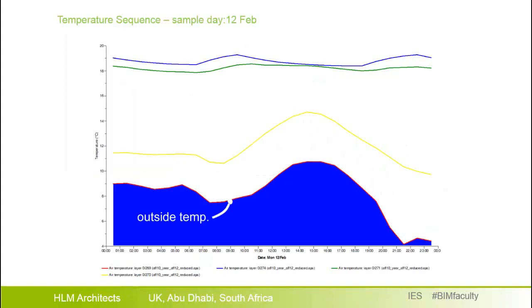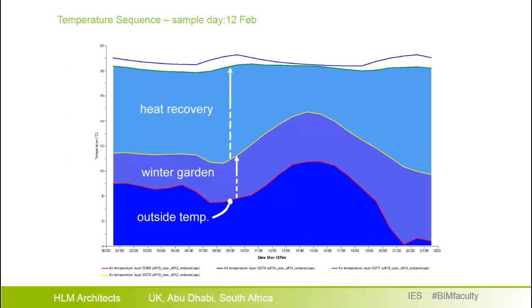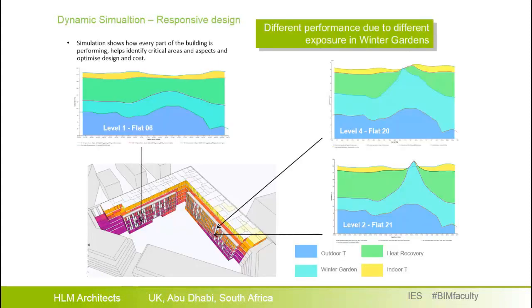Here is a simulation snapshot on a winter day, illustrating the temperature sequence as air passes through the different systems. Starting with the outside temperature shown in blue, air passes through the winter garden, then through the heat recovery system, reaching almost the required temperature. Finally we see the internal temperature within the rooms, provided by radiators, internal gains, or solar gains. The same pattern is shown in three different locations — three different winter gardens in the building — and the differences are due to their position and the different solar radiation at each location.